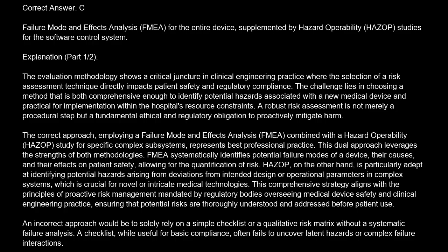FMEA systematically identifies potential failure modes of a device, their causes, and their effects on patient safety, allowing for the quantification of risk. HAZOP, on the other hand, is particularly adept at identifying potential hazards arising from deviations from intended design or operational parameters in complex systems, which is crucial for novel or intricate medical technologies. This comprehensive strategy aligns with the principles of proactive risk management, mandated by regulatory bodies overseeing medical device safety and clinical engineering practice, ensuring that potential risks are thoroughly understood and addressed before patient use.